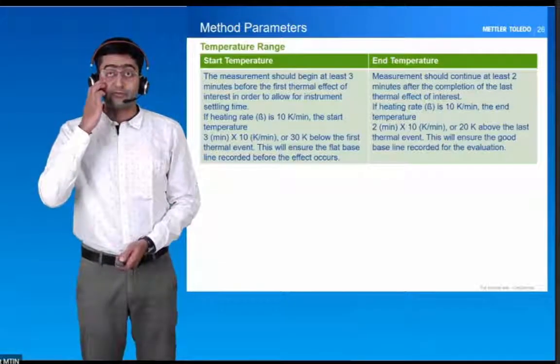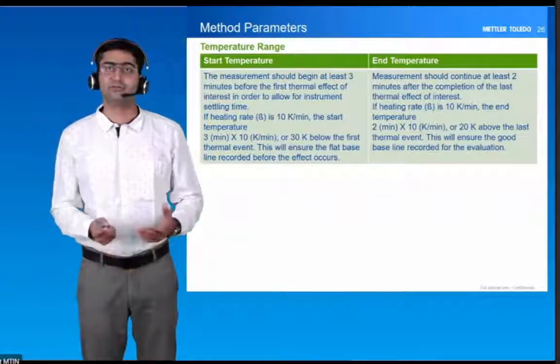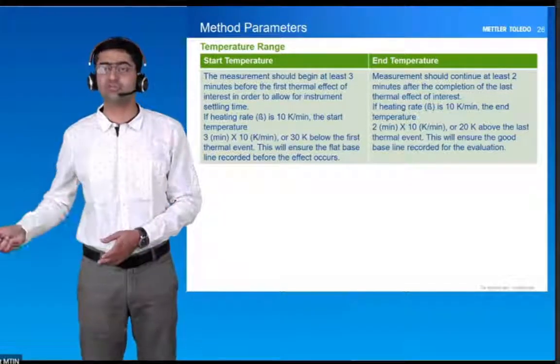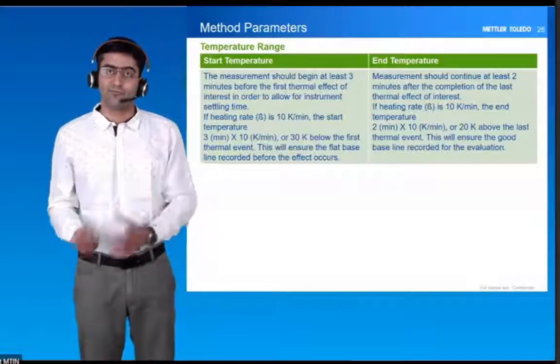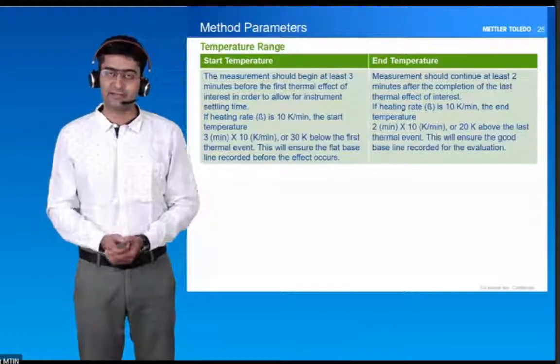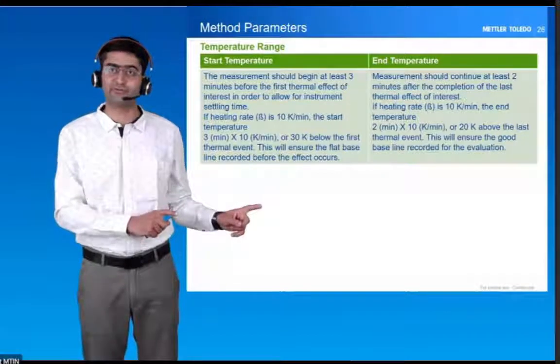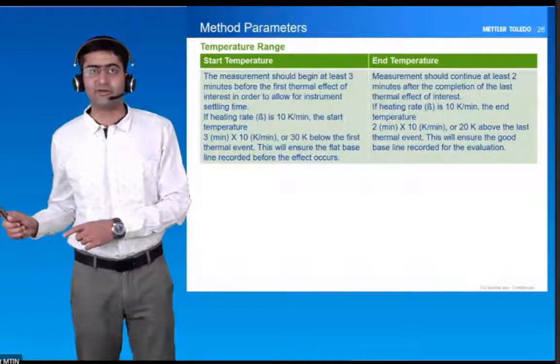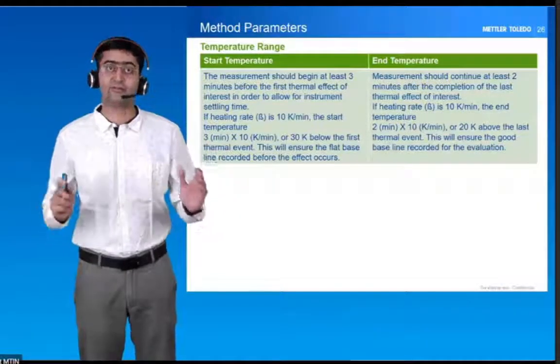Regarding method parameters — what should the start and end temperature be when designing any method? There should be three minutes before your event starts and at least two minutes after the event completes. The temperature depends on the heating rate. If the heating rate is 10 degrees or 10 Kelvin per minute, then you should have 30 degrees Celsius before the event and 20 degrees after the event in your temperature range, to capture that event completely.